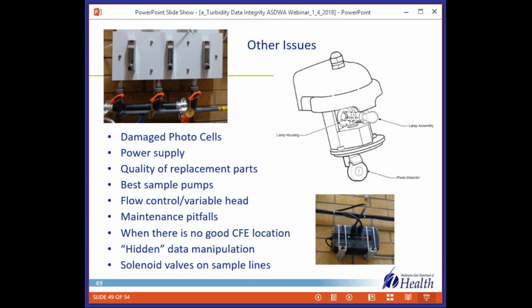Another one I called hidden data manipulation, and recently we heard from a utility that had the controllers actually lock up. They didn't realize it, but their alarm testing procedure caused the controller to go into a hold mode. And it was only when they started looking really closely at the data during an optimization exercise that they realized they were getting a flat line from those individual turbidimeters. So I think they solved that by, number one, changing their alarm testing protocol, but they also put an alarm on there to look at that fourth or fifth decimal place of the milliamp signal and tell them, you know, if it hadn't changed for 2 minutes or so, they get an alert that they can follow up on. So I think you'll find, as you look at turbidity more, you'll probably add to this list.